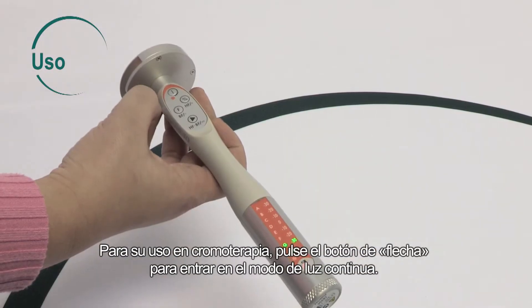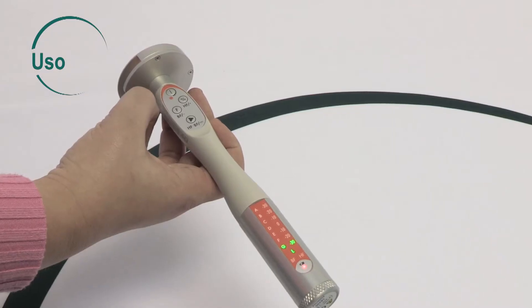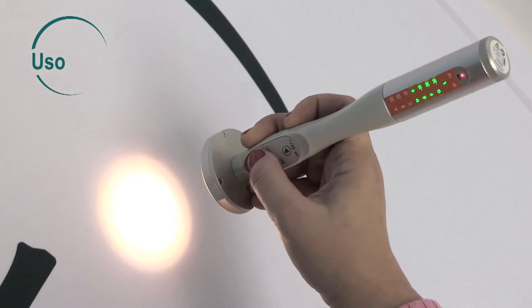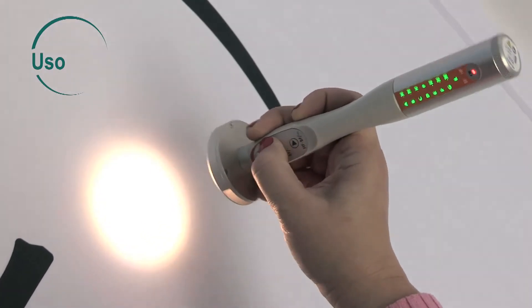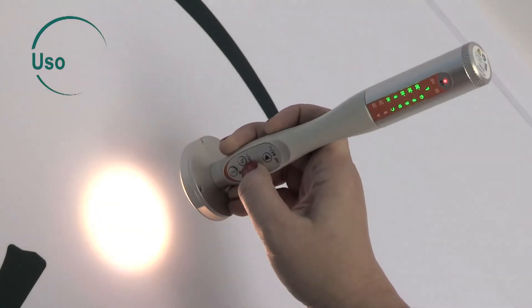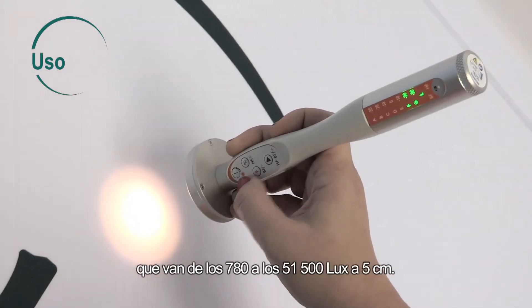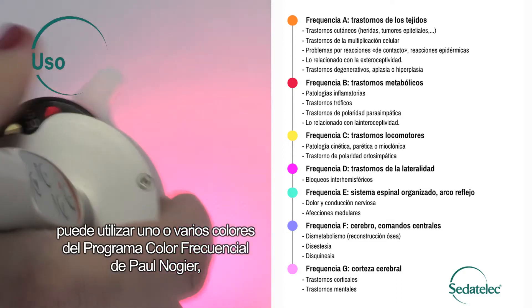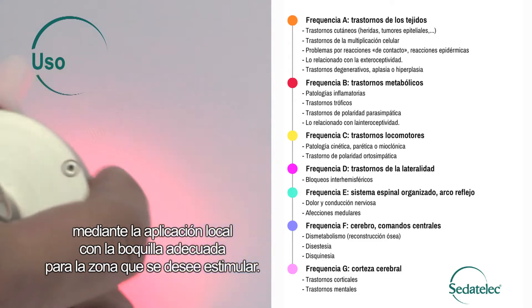For use in chromotherapy, press the arrow button to enter continuous light mode. The percent button increases the light intensity, and the F button decreases the light intensity. The Premio 40 has seven levels of intensity, from 780 to 51,500 lux at 5 cm. Depending on the disorders you are treating, you can use one or more colors from the Paul Nogier Color Frequency Program for local application with the appropriate nozzle at the zone to be stimulated.